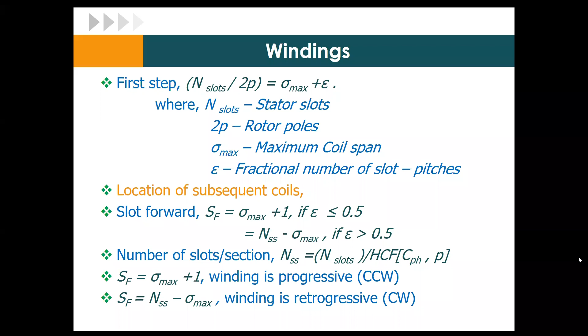If you see 4 poles, this is also taken from researchers only. If you see the coil number, this is a small example. This can be confusing also. This is 12 coil turns. Here you want to go with the first coil, and it has to be returned through the third tooth with a coil span of 2, because the difference between 3 and 1, the return coil and your go slot, is 2, so the coil span is 2 here.